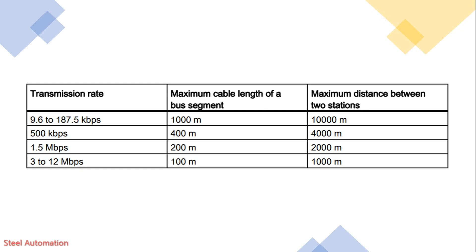For a transmission rate of 500 kbps, the maximum cable length of a bus segment is up to 400 meters, whereas the maximum distance between two stations using an RS-485 repeater is up to 4000 meters. For a transmission rate of 1.5 Mbps, the maximum cable length of a bus segment is up to 200 meters, and the maximum distance using an RS-485 repeater is up to 2000 meters.